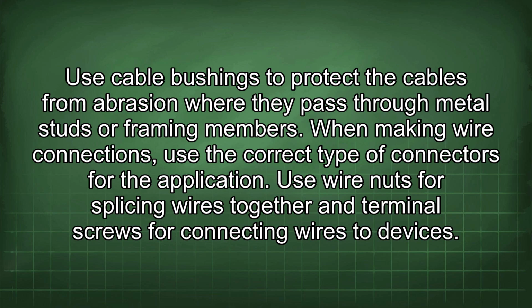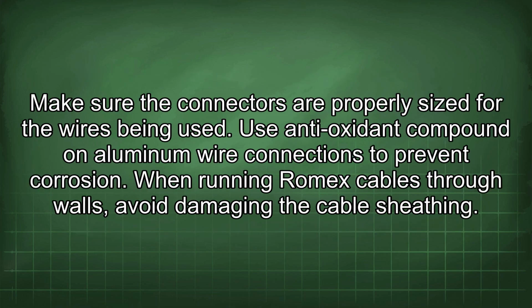When making wire connections, use the correct type of connectors for the application. Use wire nuts for splicing wires together and terminal screws for connecting wires to devices. Make sure the connectors are properly sized for the wires being used. Use antioxidant compound on aluminum wire connections to prevent corrosion.